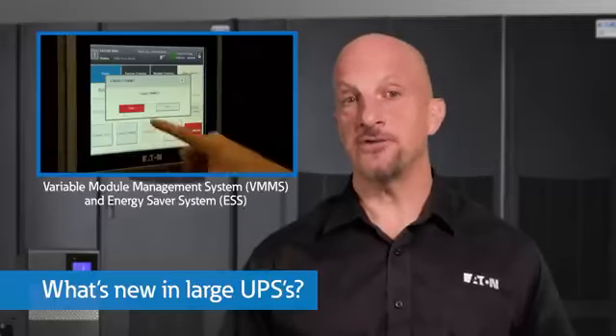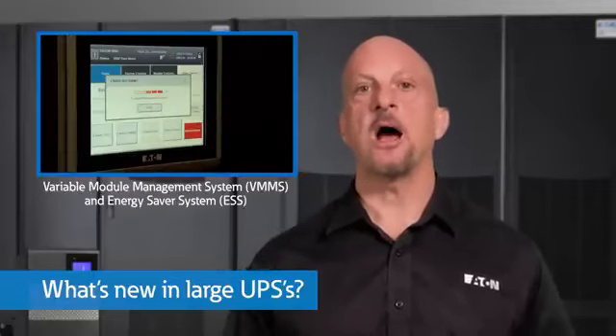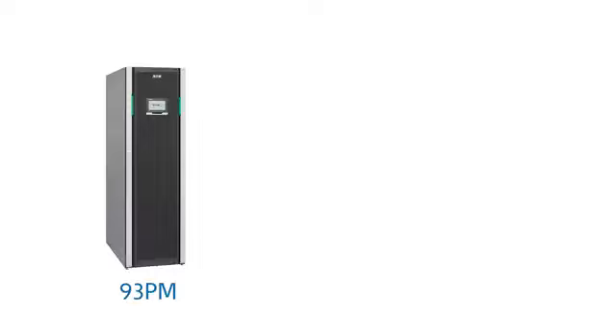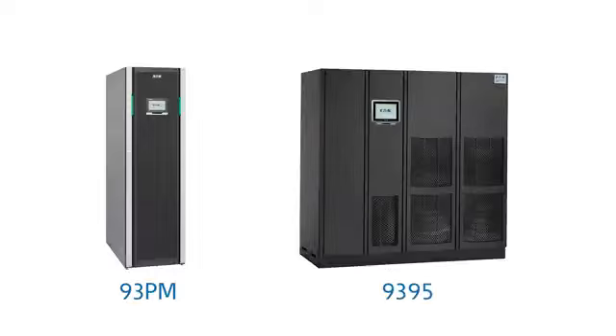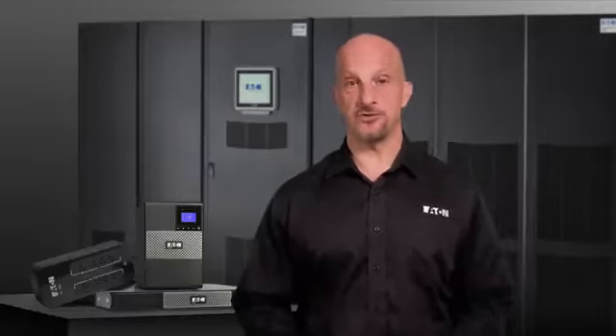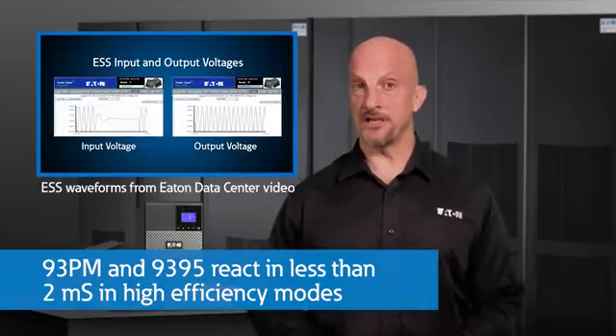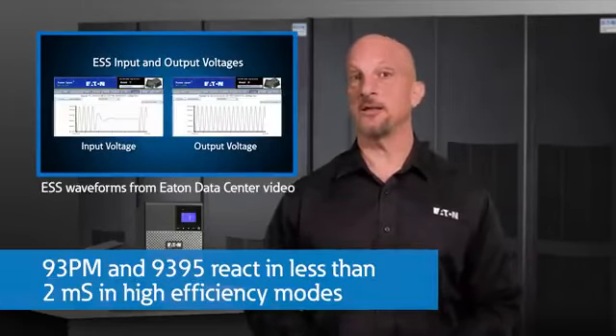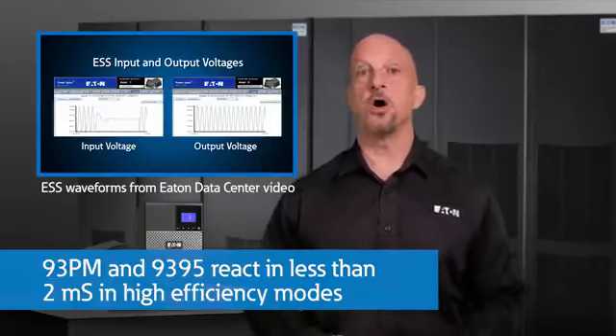For larger three-phase applications, most UPSs are double conversion units. However, newer technology UPSs like Eaton's 93PM and 9395 offer full double conversion and complete isolation from primary to secondary, but also offer higher efficiency modes like energy saver or variable module management. These units act like high-speed hybrid versions of line interactive and double conversion UPSs, but react in less than 2 milliseconds to ensure computer power supplies are protected, even during a full power outage. Although these units are highly efficient running in double conversion mode, you can save additional money by operating with these higher efficiency modes for large UPS systems.